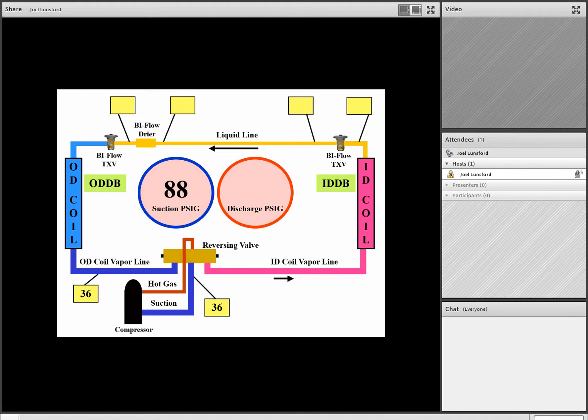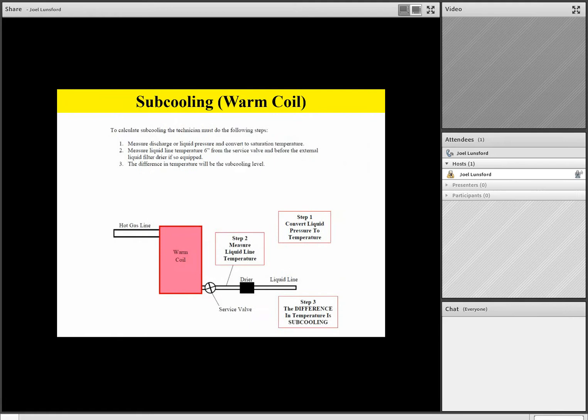Okay, at this time, let's go ahead and talk about subcooling in the warm coil. And remember, team, if we can find coil condition, flooded, starved, or normal, on the outdoor coil and the indoor coil, in any mode of operation, it makes us a better troubleshooter. And we'll be tying this all together into a big diagnostic picture when we start getting into Module 6.